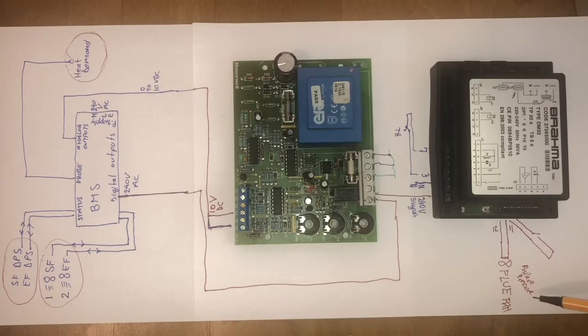If the positive pressure is okay, this switch will close the circuit. If the circuit is closed within a specific time, then that means the signal goes back and the Brahma controller will know that the flue fan is healthy, it's running, because if the fan doesn't run, you don't have a positive air pressure and then the switch is open. If you have a positive pressure, you have an air pressure, then the switch will close, and then the Brahma controller will know the fan is running. That's the witness. So we have the thermostat close the circuit, and then the fan starts, the DPS closes the circuit, which means the flue fan is running.